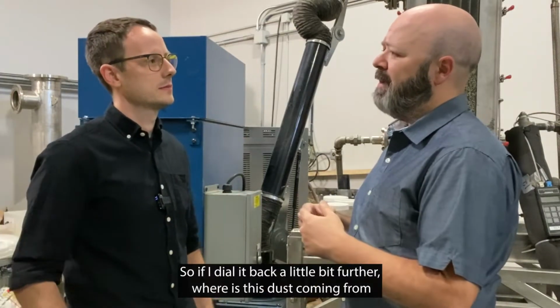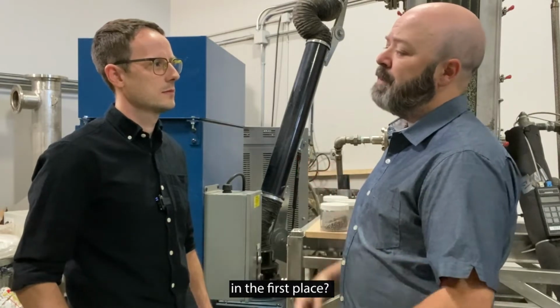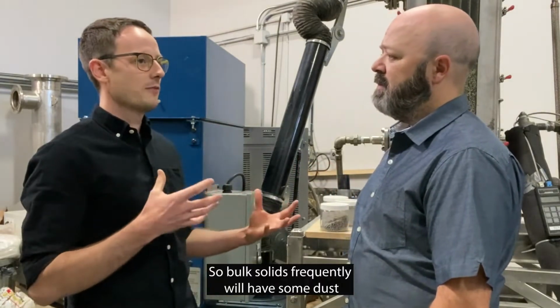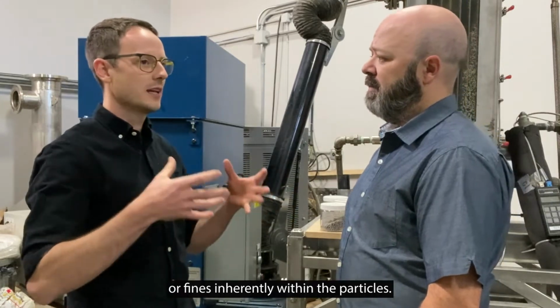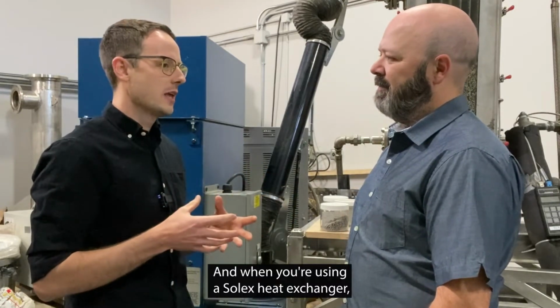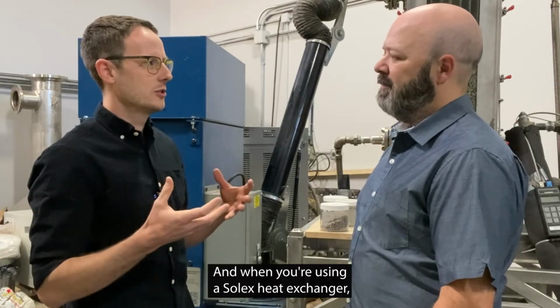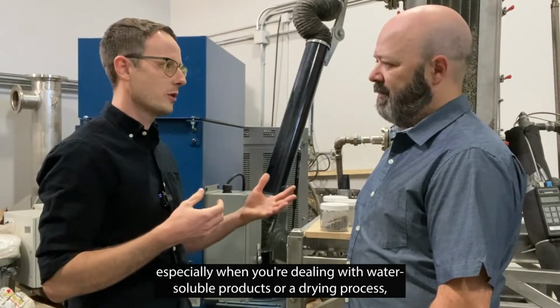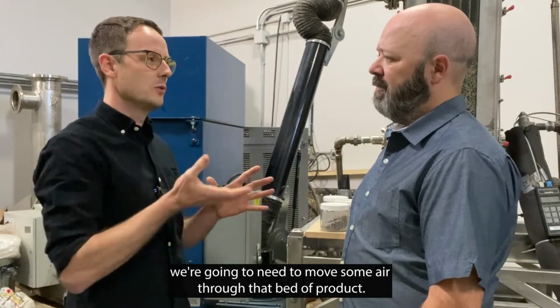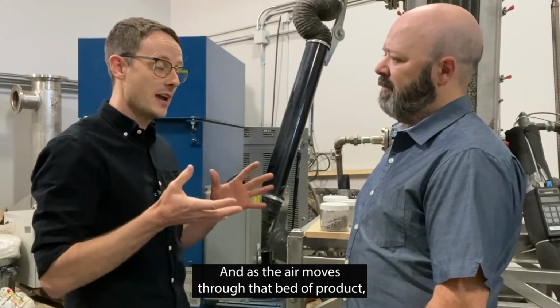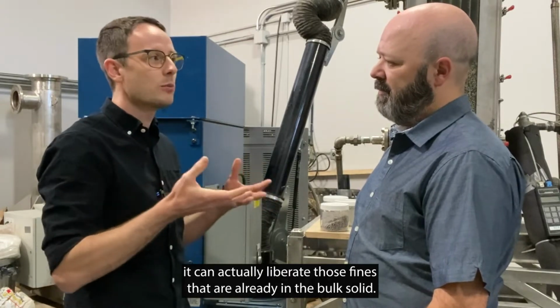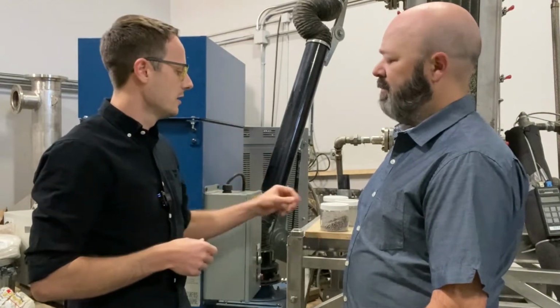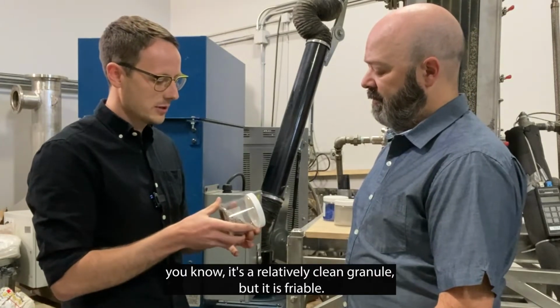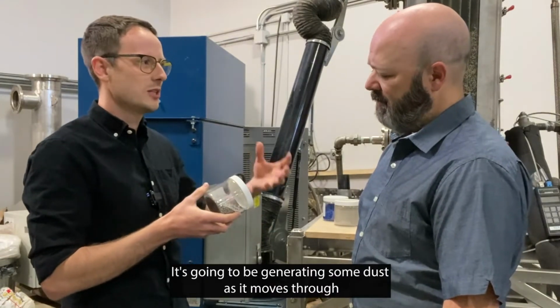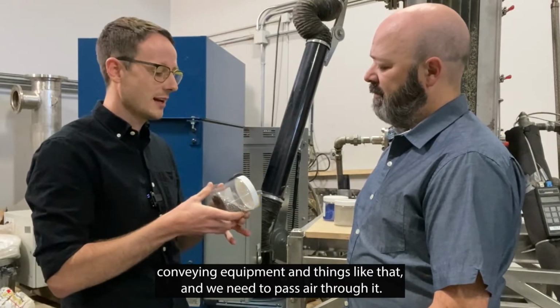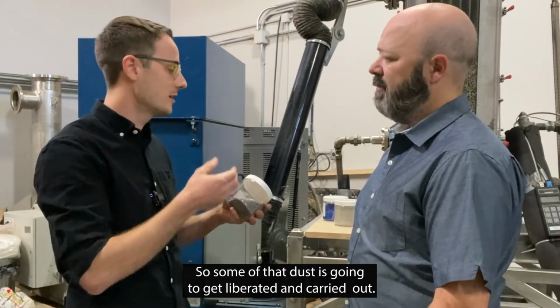All right. So if I dial it back a little bit further, where is this dust coming from in the first place? Bulk solids frequently will have some dust or fines inherently within the particles. And when you're using a Solex heat exchanger, especially when you're dealing with water-soluble products or a drying process, we're going to need to move some air through that bed of product. And as the air moves through that bed of product, it can actually liberate those fines that are already in the bulk solid. Say, for instance, with a fertilizer granule, it's a relatively clean granule, but it is friable. It's going to be generating some dust as it moves through conveying equipment and things like that, and we need to pass air through it. So some of that dust is going to get liberated and carried out.